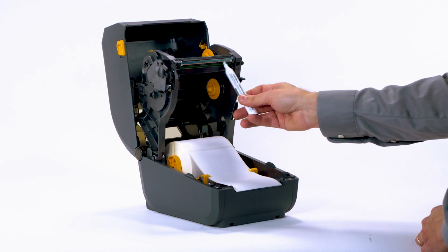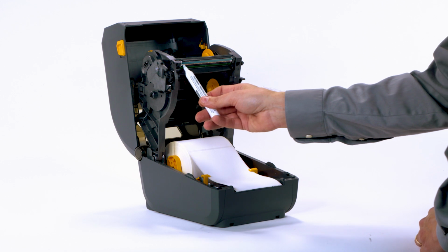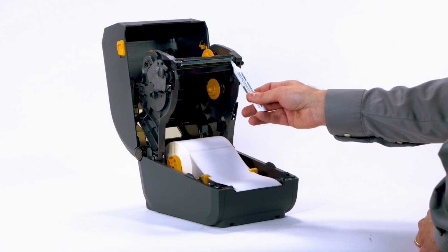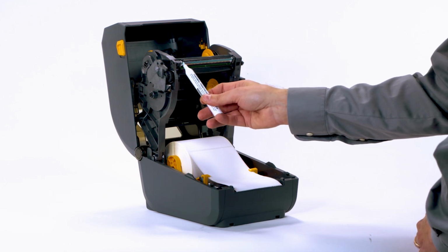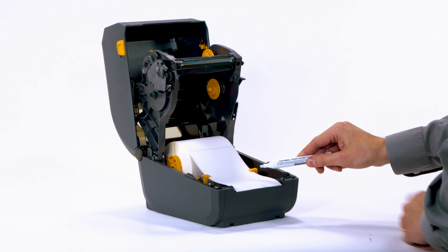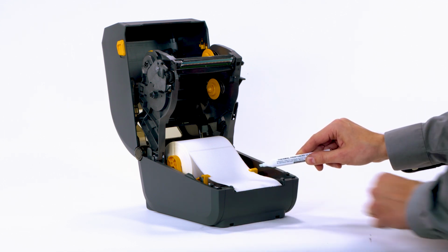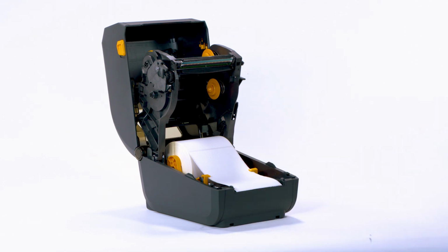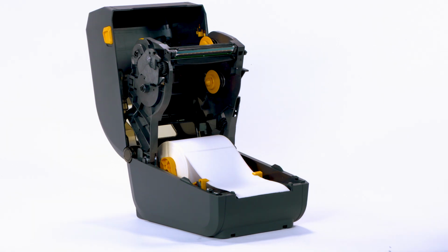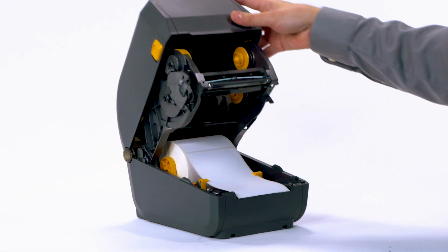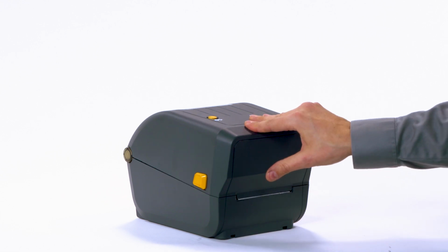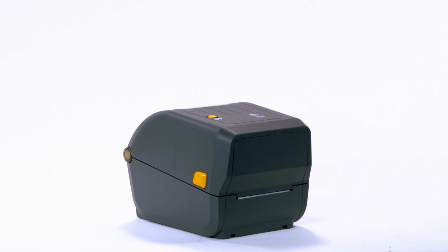You can also use a lint-free cloth or swab moistened in 99.7% isopropyl alcohol. Do not use the print head cleaning pen on the platen roller or other printer parts. Allow the solvent to evaporate. Clean the print head whenever you replace the ribbon on a thermal transfer printer, or when you replace the labels on a direct thermal printer. Close the printer. We recommend using a Zebra preventive maintenance kit.